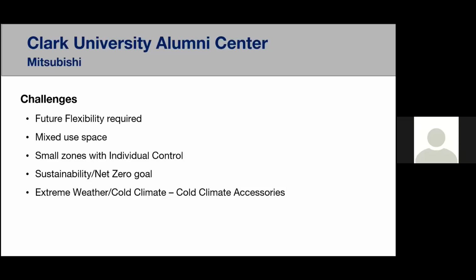And also one of the challenges was small zones with individual control. So we really needed to zone this building. In a lot of cases, if you had a VAV system, the amount of zones we did would not have worked whatsoever. It would have actually been very expensive. And that's why we went with VRF, because, believe it or not, VRF was a cheaper alternative for putting in all these small zones for these small exterior office spaces.